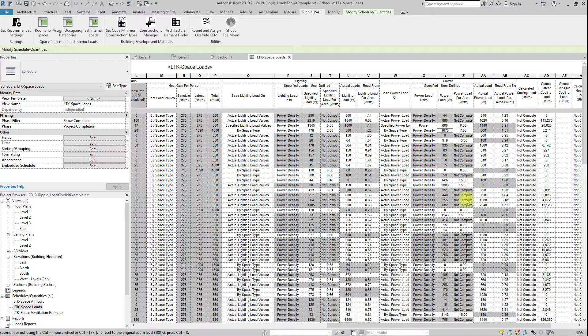There are two ways that Revit passes the thermal properties of building elements into a GBXML, or the Internal Loads tool. One way is to override the thermal properties of the element category, and the other way is to use the actual thermal properties defined in the element.